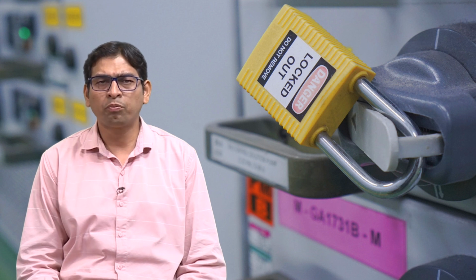Tagout devices provide a visual warning that work is being performed on a machine or piece of equipment. The tags indicate the people who are working on the machine and can also indicate why the equipment is out of service. Remember, tags only provide information alone; they cannot secure an energy isolation device. So they should be used with locks whenever possible.